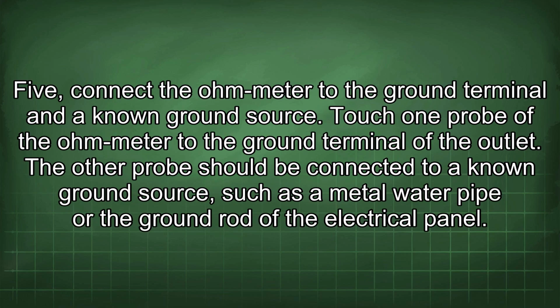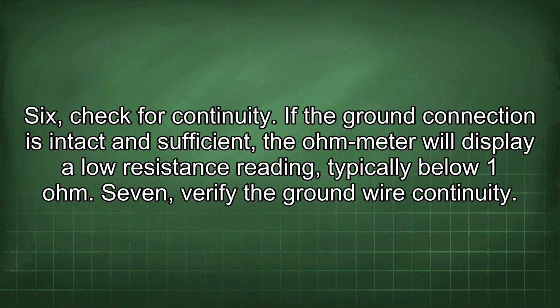5. Connect the Ohm-Meter to the ground terminal and a known ground source. Touch one probe of the Ohm-Meter to the ground terminal of the outlet. The other probe should be connected to a known ground source, such as a metal water pipe or the ground rod of the electrical panel. 6. Check for continuity. If the ground connection is intact and sufficient, the Ohm-Meter will display a low resistance reading, typically below 1 ohm.